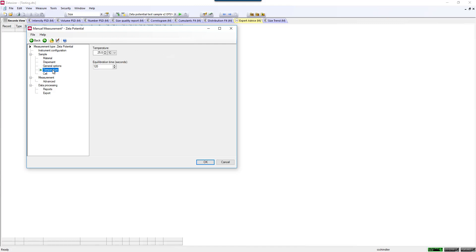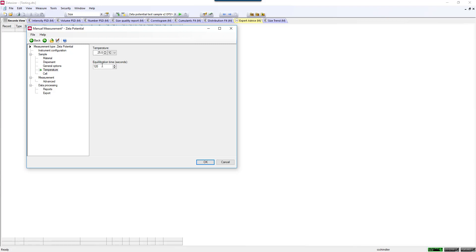The temperature is also important. You can select the temperature that you would like to make the measurement at, and then also an equilibration time. Equilibration time can vary from zero seconds all the way to a few minutes, just depending on how different your sample is from the temperature that you would like to make the measurement at. The instrument automatically heats and cools with the Peltier around your sample, but we need to make sure that the sample that you put in comes to the exact temperature as the instrument.